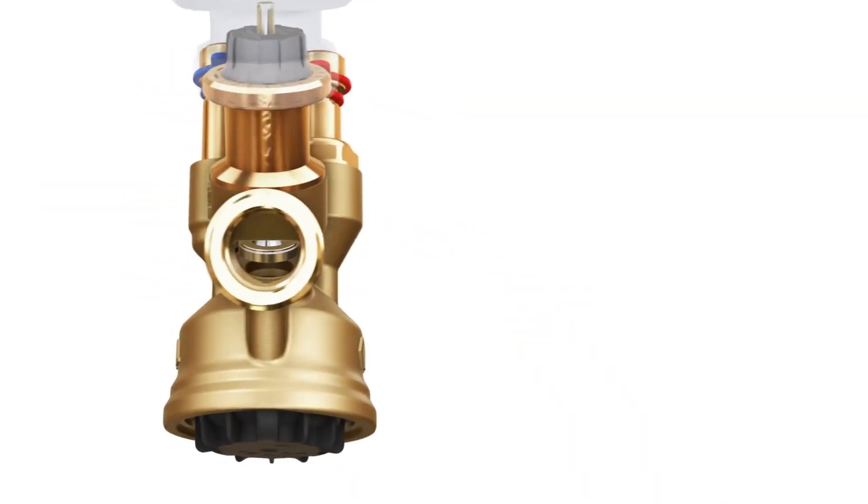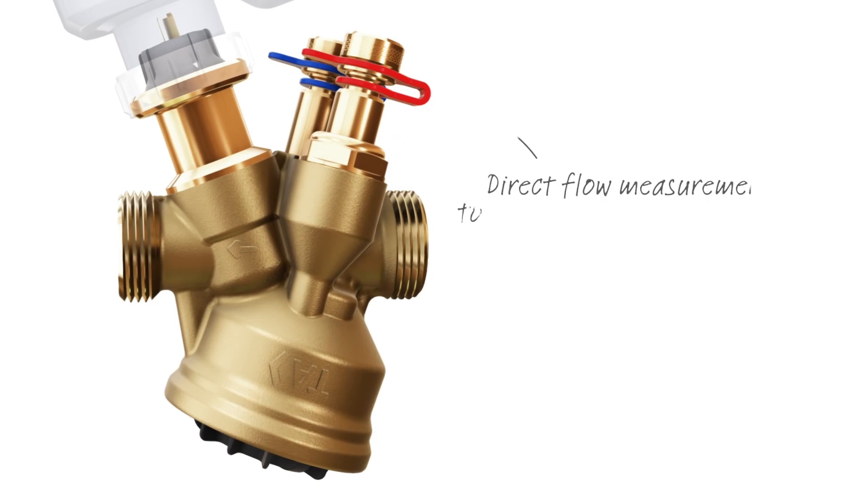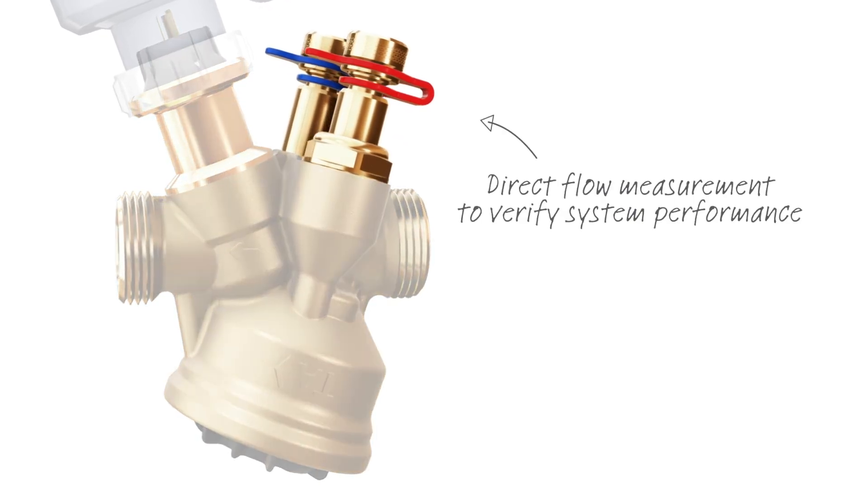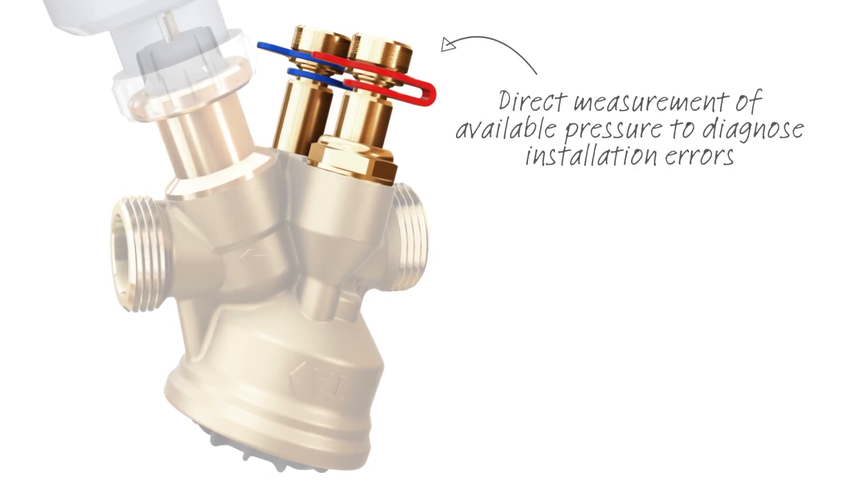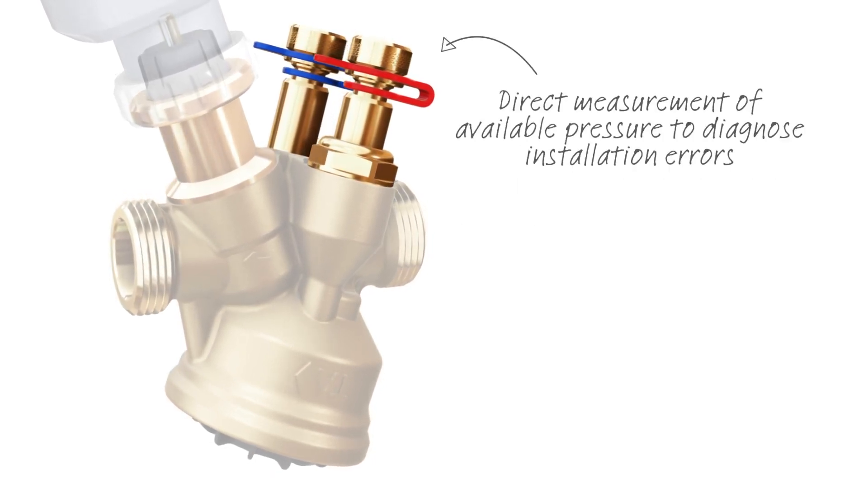But let's look at the other unique features. With TA modulator, you can measure the true flow through the valve to verify the system performance, as well as measure the available differential pressure to diagnose possible installation errors.